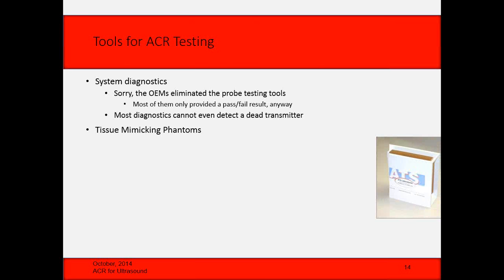So you can see the problem here, if you know about test theory, that you have to have a testing device that is twice as good as, or twice as accurate as, what you're trying to measure. Well, it's physically impossible to put the pin targets into the phantoms close enough that we could measure this. So that's the issue with phantoms. And in fact, you could do all the performance testing that would tell you the condition of the system and the probes, but you have to buy about $150,000 worth of phantoms.